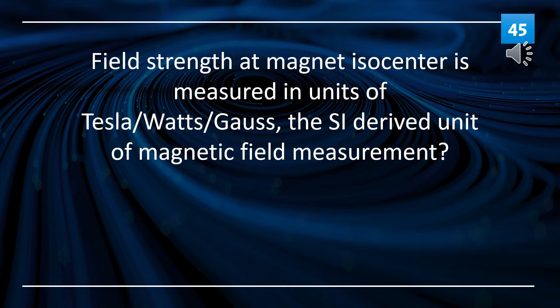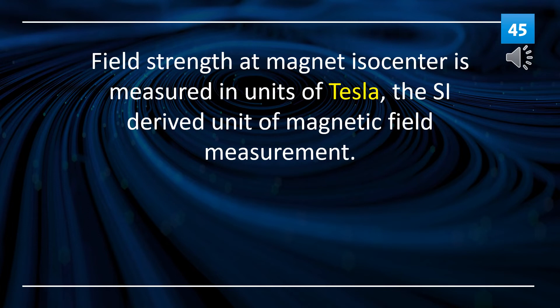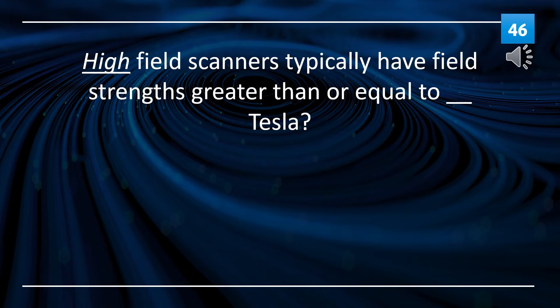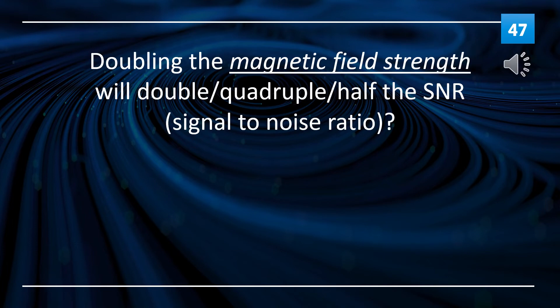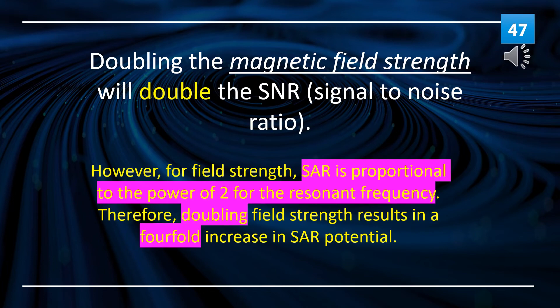Field strength at magnet isocenter is measured in units of Tesla, the SI-derived unit of magnetic field measurement. High field scanners typically have field strengths greater than or equal to 1.5 Tesla. Doubling the magnetic field strength will double the SNR. Note: don't mistake this for SAR — doubling field strength will quadruple SAR.